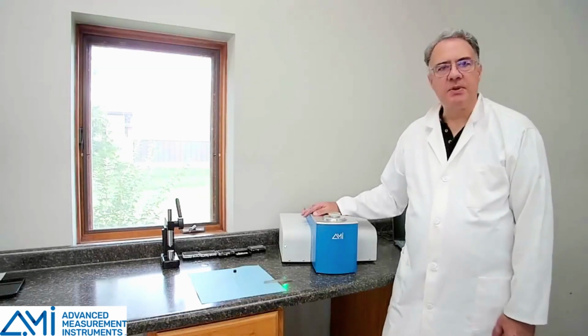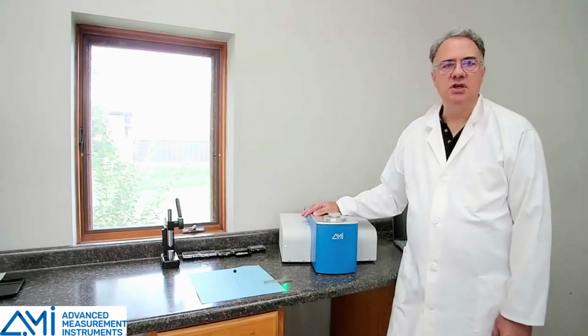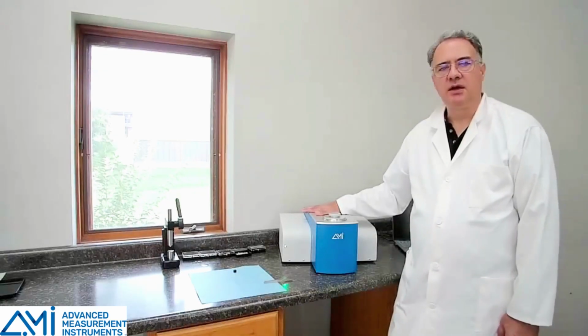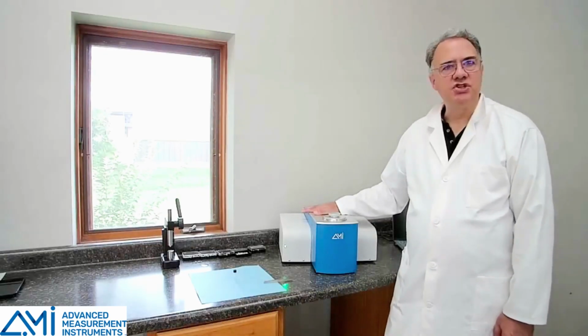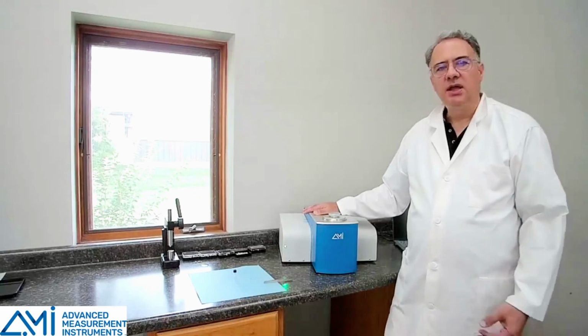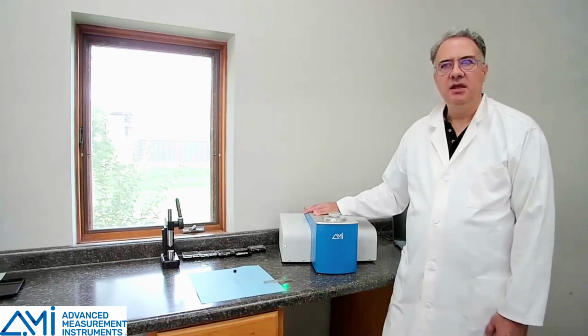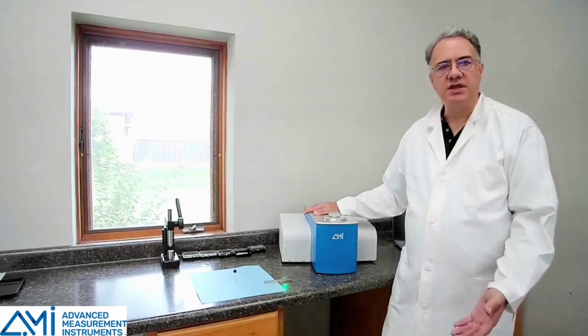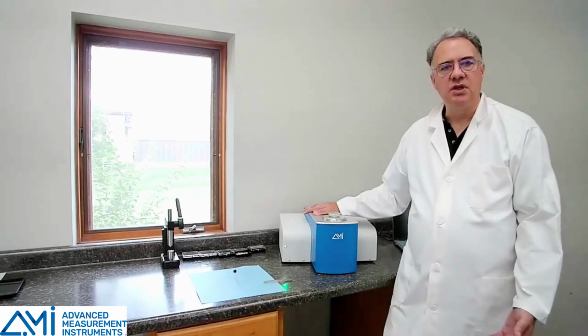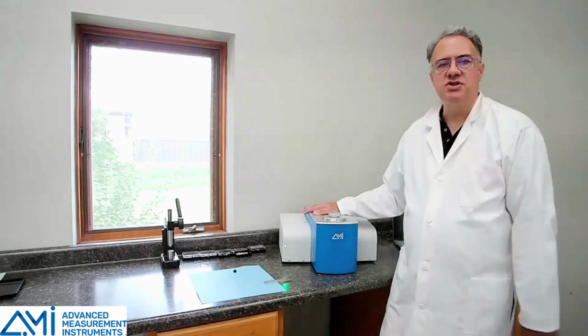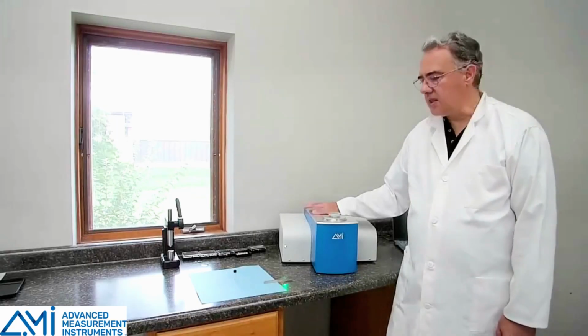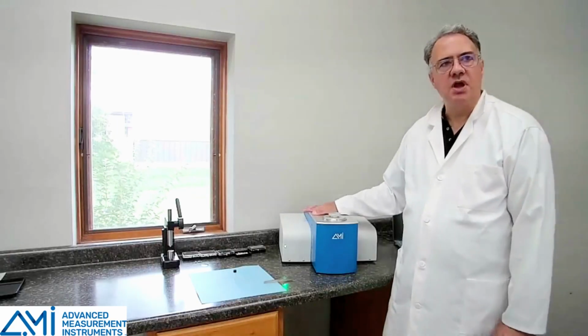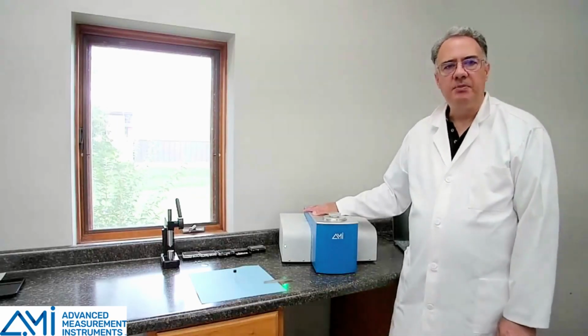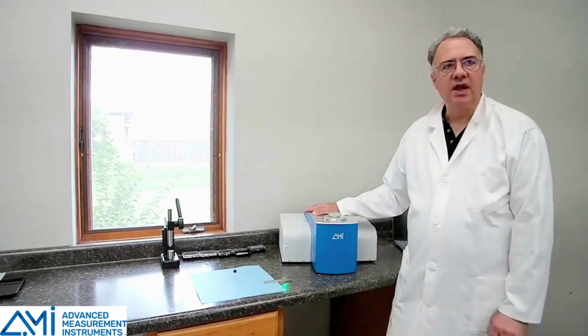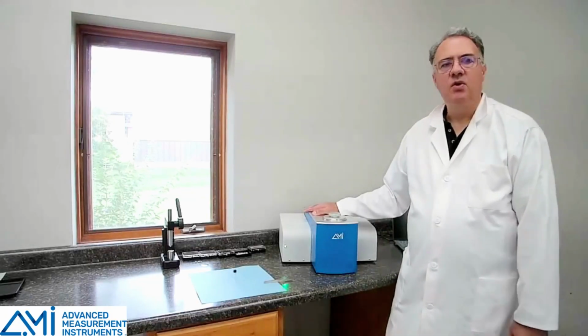So what we recommend is that periodically, depending on your application, you run periodic calibration checks on the instrument, or if for some reason you notice that your standards that you've been running or your samples you run come up with an unusual change, then you would run a calibration check and, if necessary, a calibration. Calibrating our instruments is extremely easy, and we'll cover that when we cover the software, but this gives you an idea of kind of the importance of calibration and when not to calibrate.